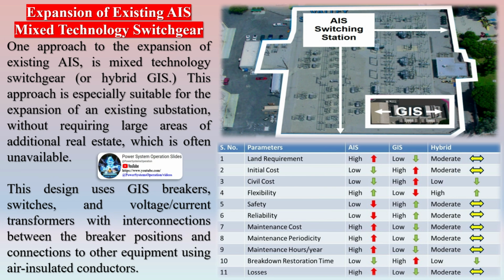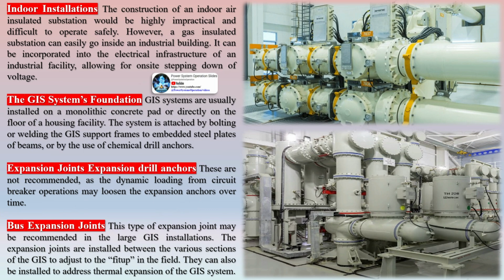One approach to the expansion of existing AIS is mixed technology switchgear, or hybrid GIS. This approach is especially suitable for the expansion of an existing substation without requiring large areas of additional real estate, which is often unavailable. This design uses GIS breakers, switches, and voltage and current transformers, with interconnections between the breaker positions and connections to other equipment using air-insulated conductors.